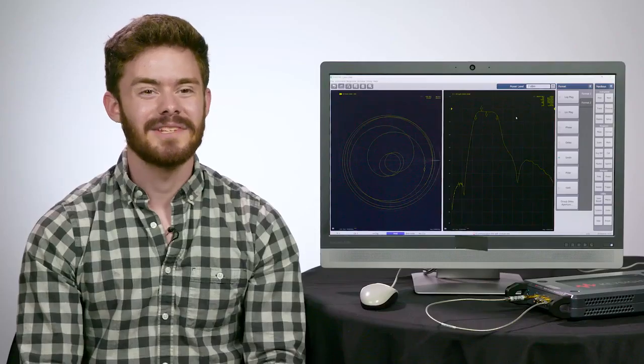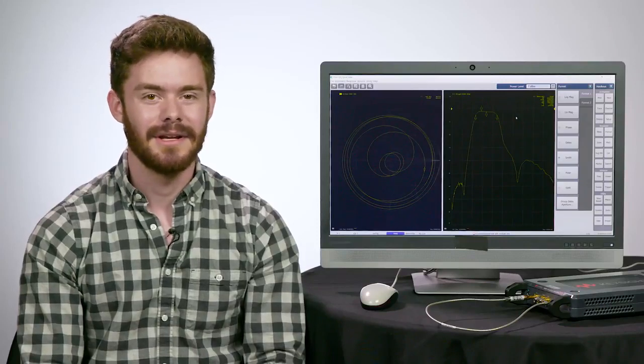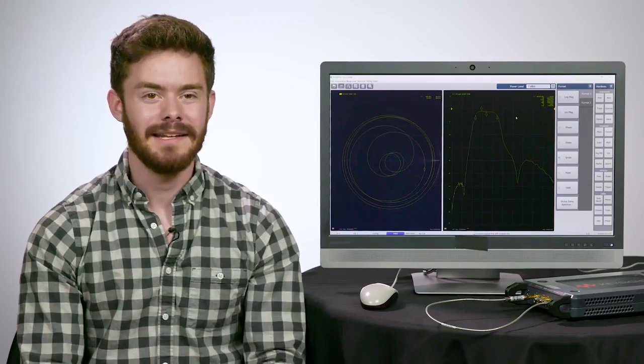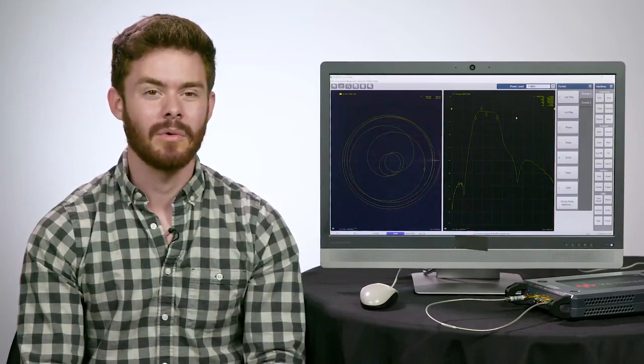The E-cal module is used for this calibration to remove system errors like the effect of test cables. Wait until the LED of the E-cal module turns green, indicating that it has warmed up enough in order to correctly calibrate. Once the module is connected, start the calibration by going to the CAL menu, selecting Other CALs, and E-cal.